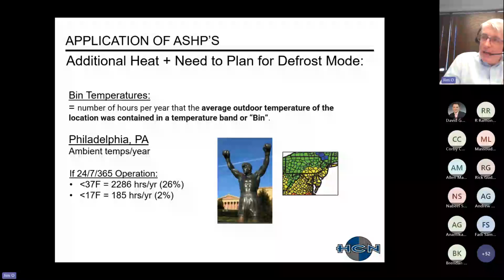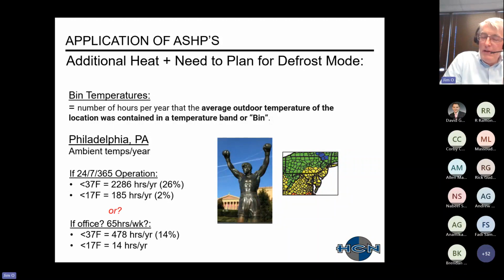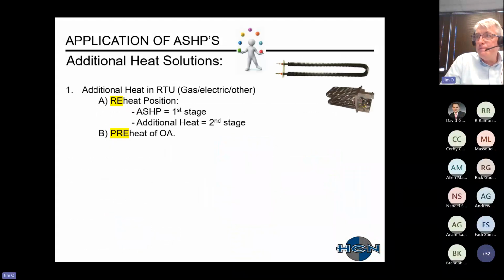So if you're looking at Philadelphia, if you have 24/7, 365 operation, just from the bin temperature about 25% of the time you're below 37, and 2% of the time you're below 17. But then if you compare it to an office, you'd still have approximately 15% of the hours below 37 degrees, where you should plan or just understand that defrost is going to occur. All right. Okay, thanks. So what are we going to do to try to minimize our defrost?